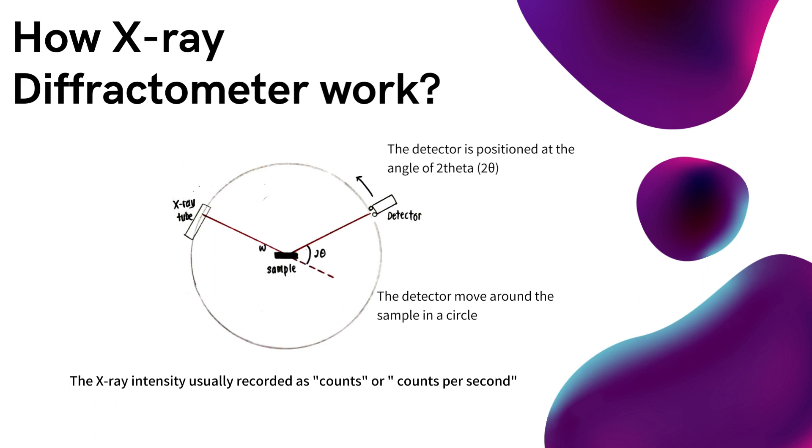The detector moves around the sample in a circle and is positioned at the angle of 2 theta, thus it will record the number of X-rays observed at angle of 2 theta. The X-ray intensity is usually recorded as counts or counts per second.